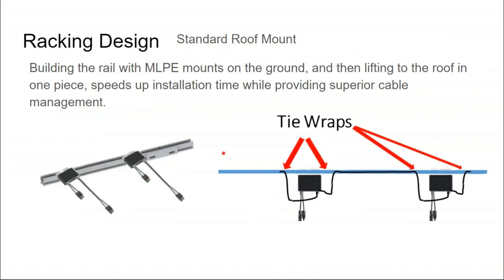Here we have module level power electronics—voltage regulators that go up behind every solar module. They add a lot of wiring underneath the array because every module plugs into them, and the module leads aren't sized for the optimizer, so there's a lot of slack. There's also optimizer-to-optimizer slack since they're designed for both portrait and landscape, so you end up with loose cable upon loose cable on the roof that's very hard to manage. What I do is take this U-channel and measure out on the ground where every optimizer will go on that rail, building it all on the ground with the cable pre-managed before lifting these sections up to the rooftop.